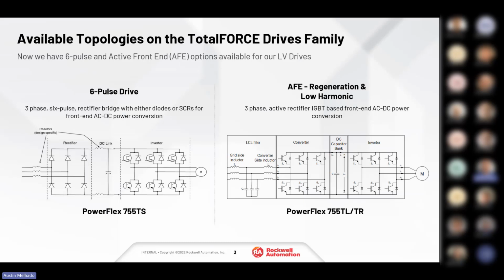So just a little bit on the power topologies. On the right is AFE, which stands for active front end. What that entails is that typically on a VFD, we have 6 SCRs on the front end of the drive, rectifying our AC voltage to go to our DC bus, the DC capacitor bank. In this case, however, regarding the TL and the TR, our active front end drive has 6 IGBTs on the front, thus allowing us to create a very low harmonic drive. So we control the front end of the rectifier, which is connected to the AC mains, to ensure that harmonics are kept to the lowest possible. Total harmonics are limited to 3 to 5% over the operating range of the VFD.